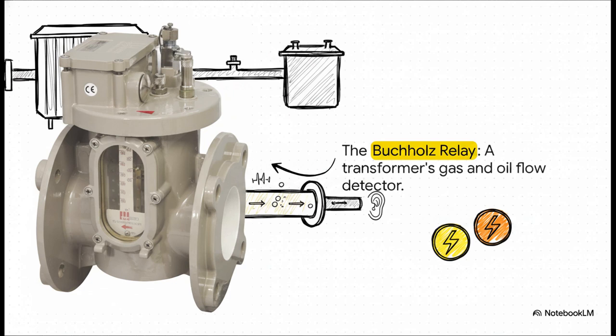It's basically a gas and oil flow detector that sits in the pipe between the main transformer tank and its oil reservoir up top, which is called the conservator. You can think of it as a little watchdog, listening for whispers of trouble from inside. And what's so cool about it is that this one simple device actually gives you a two-stage warning.